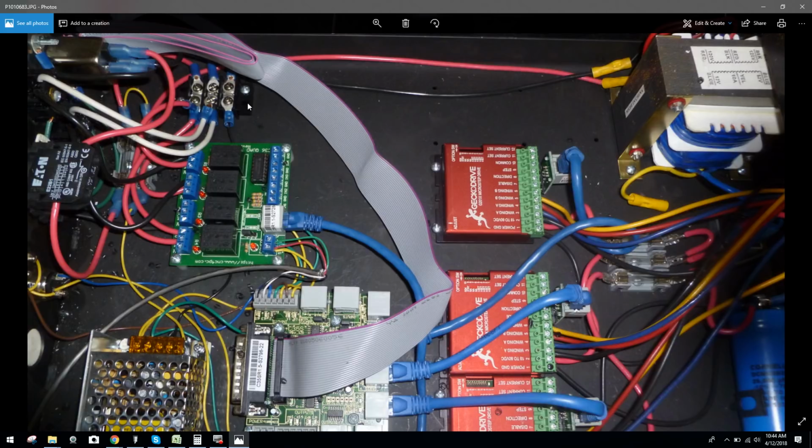One of the biggest issues when using a terminal block is you want to make sure that if you have multiple connectors going to the terminal block that all need to be on that same pin, you should be using a splitter. That's the correct process to do. You don't piggyback quick connects in order to do this. Why I'm saying that? Because some guys out there are going, well, you're being anal. No, I'm not being anal. It's just I understand the type of electronics we're dealing with here.